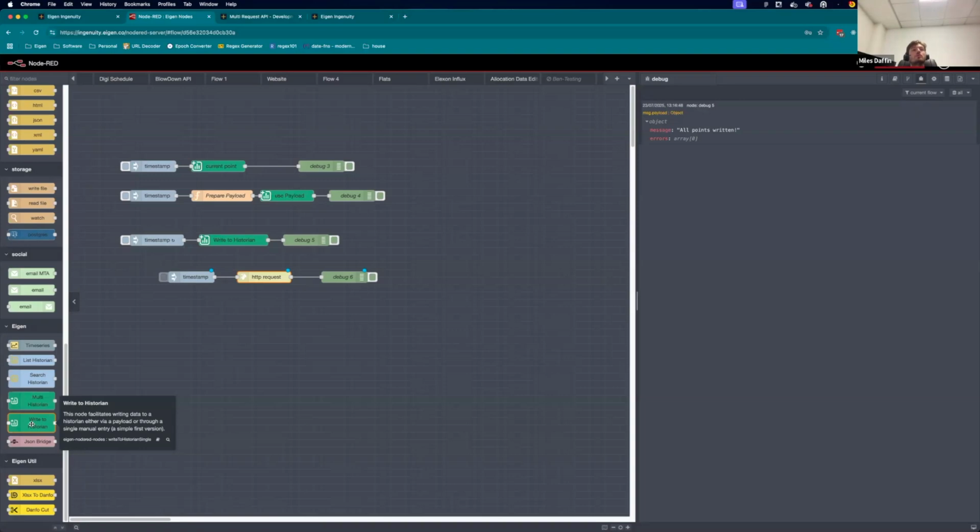Going back to the point I made earlier, the blowdown use case was something like this. You'd query the historian and capture all this external data, so all the timings to get to certain pressures, or at 50%, and you might query the asset model to grab some external metadata around that. You bundle it all into a nice little JSON event and then post that into the database. Once it's there, you can use another set of APIs to build an advanced dashboard. So you might want to see the latest alarm for each segment, and then see the history. We're doing something very similar with well tests using that exact same method.